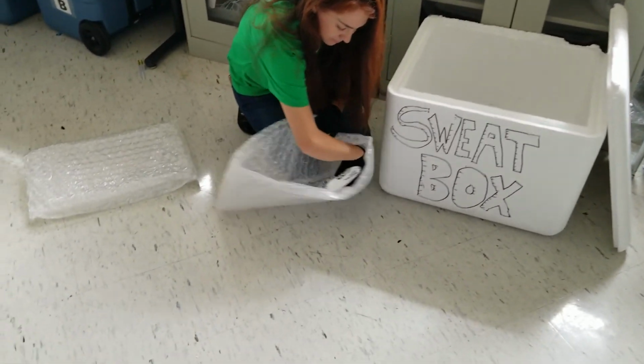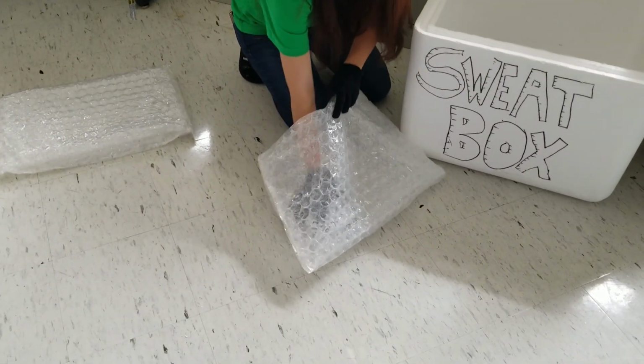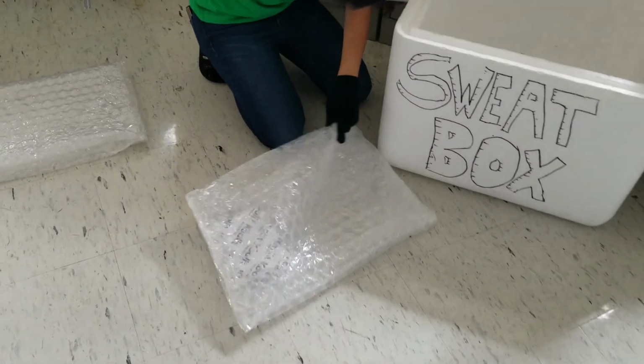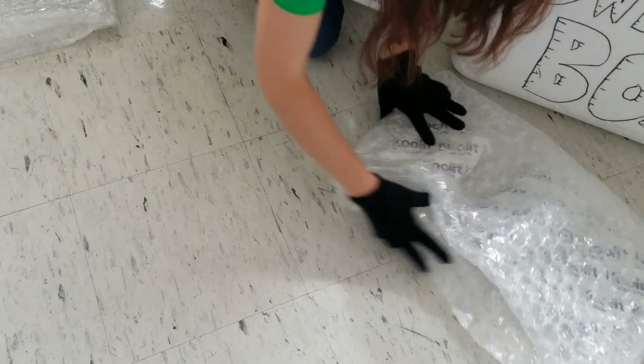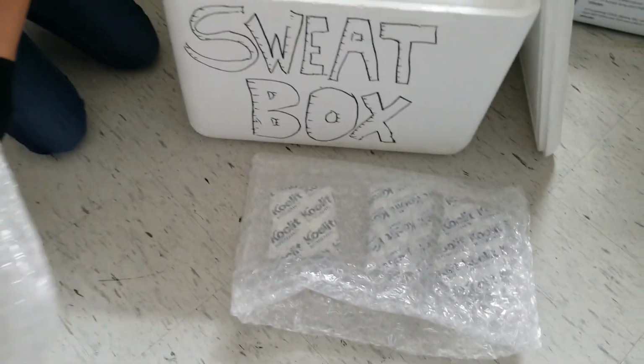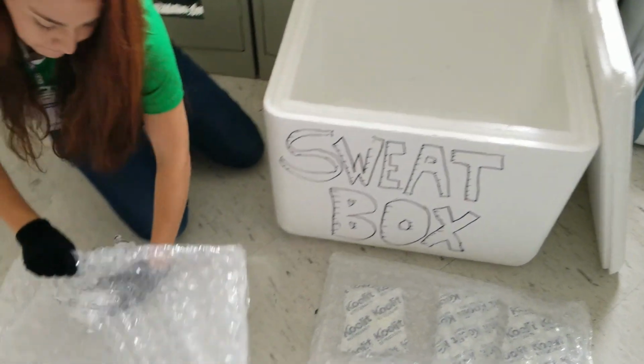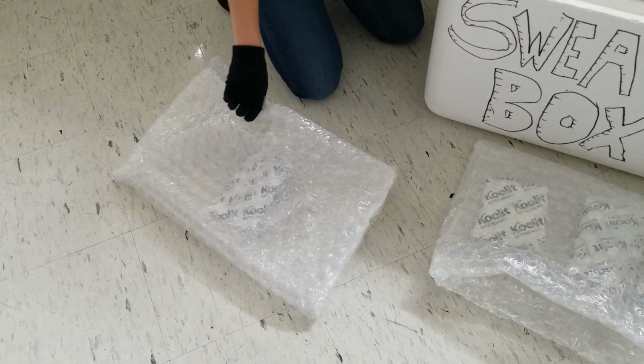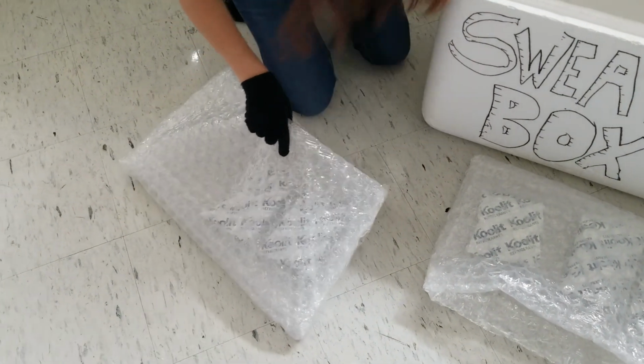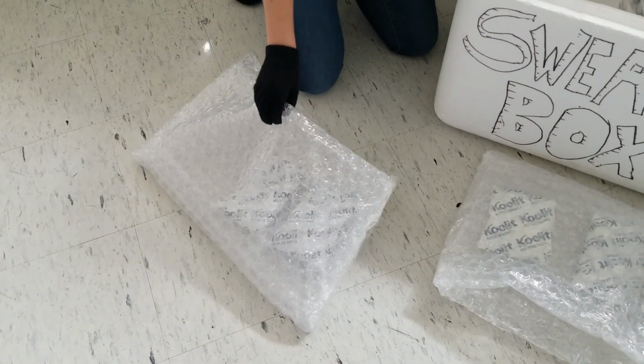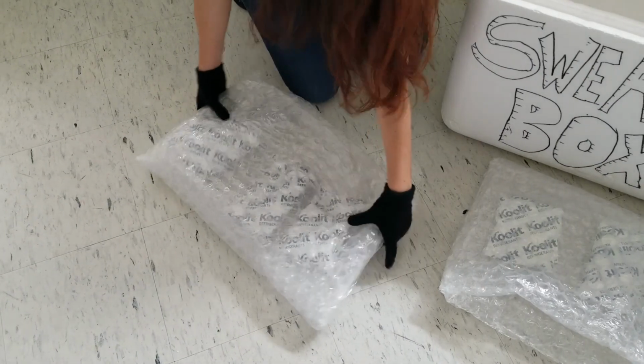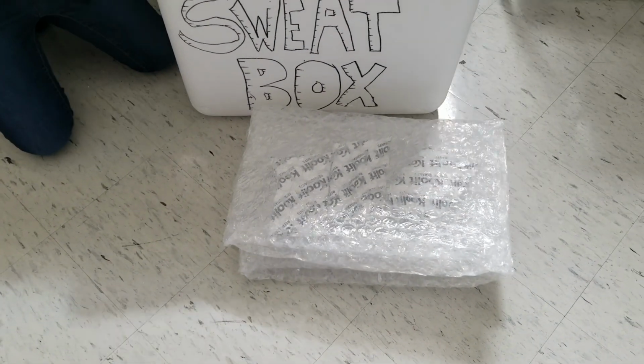We will start packing the vaccines by placing 3 ice packs into each of the 2 bubble wrap sleeves. Please note that the amount of ice packs used in each cooler will be dependent on how many boxes of vaccines will be in the cooler. A general guideline of how many ice packs per amount of vaccine will be provided. Another factor to consider is that substantially large quantities will be placed in a larger cooler. However, the premise is the same.